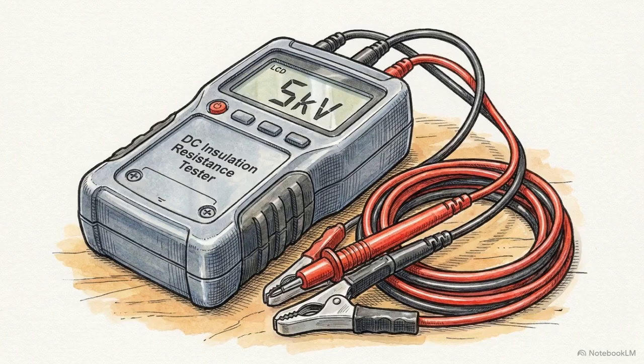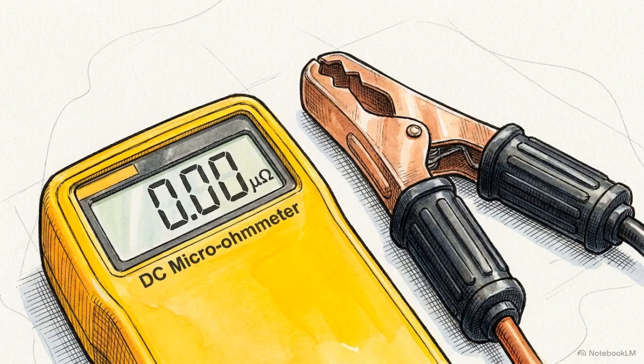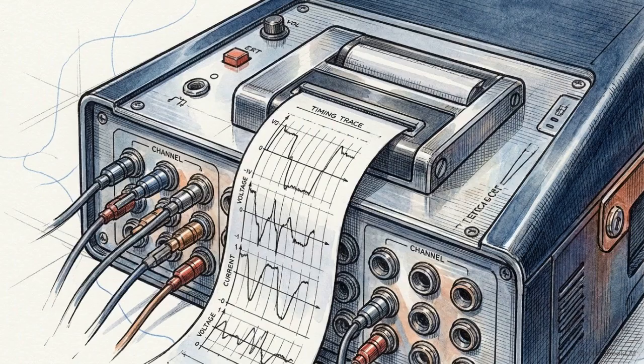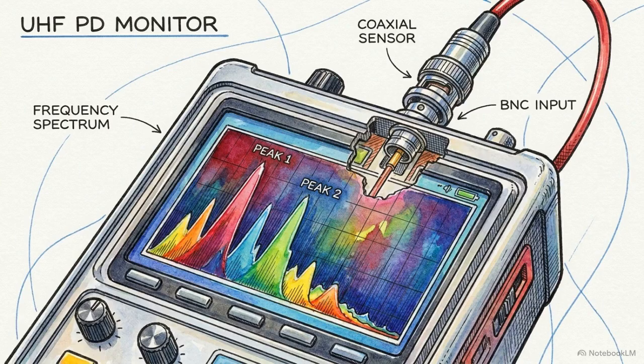The 5 kV DC insulation resistance tester proves the integrity of phase-to-ground and phase-to-phase insulation. The 100 amp DC micro-ohm meter measures millivolt drops to validate low-resistance current paths across main contacts. The circuit breaker analyzer maps mechanical operating times down to the millisecond, and the portable UHF monitor detects partial discharge emissions that indicate microscopic insulation flaws.